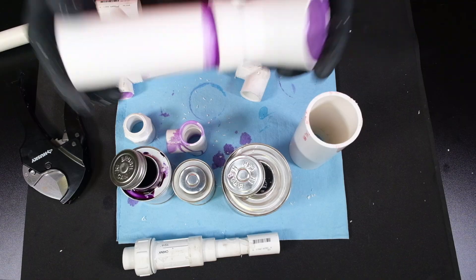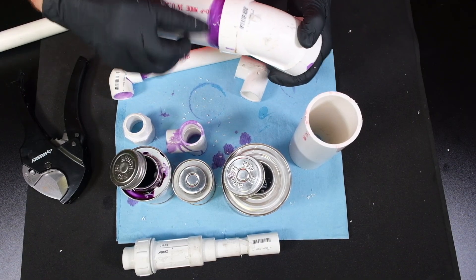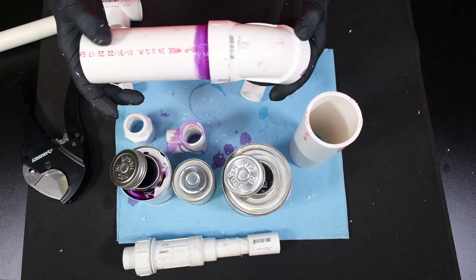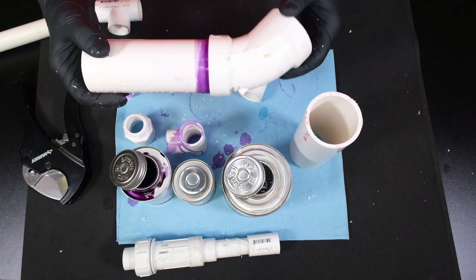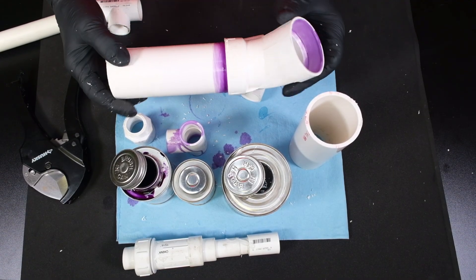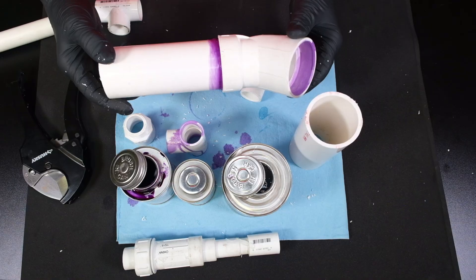Make sure you've got glue all the way around your joint. That's a good glue joint right there. It ran all the way around it. Inside the pipe it looks good. That's what you want a PVC joint to look like. Some guys want this primer line a little further back and that's okay. I had one plumber that was so good at it he could make where there was barely an eighth inch at it. He'll know who I'm talking about if he's watching this video. And he did a great job.